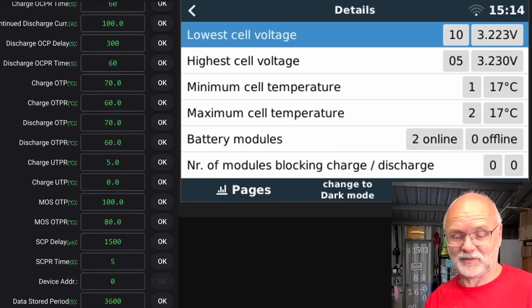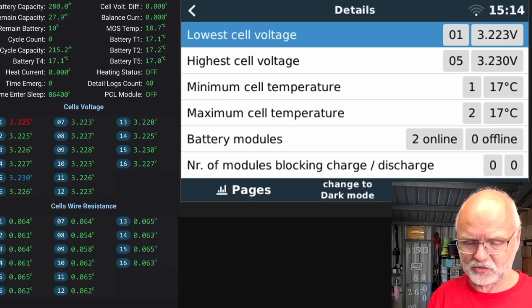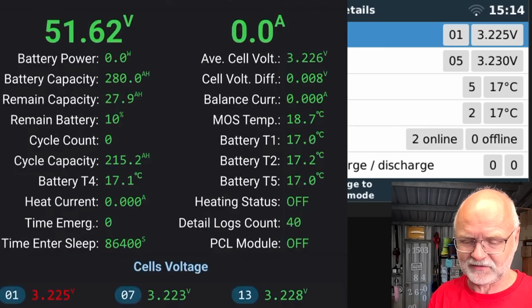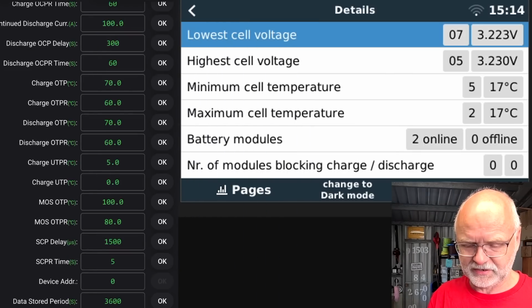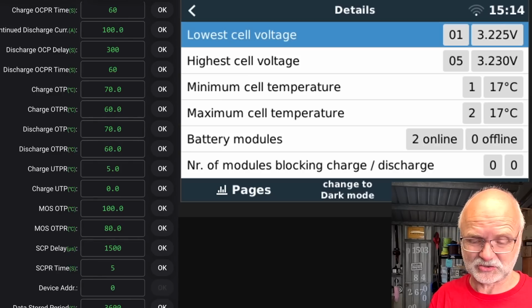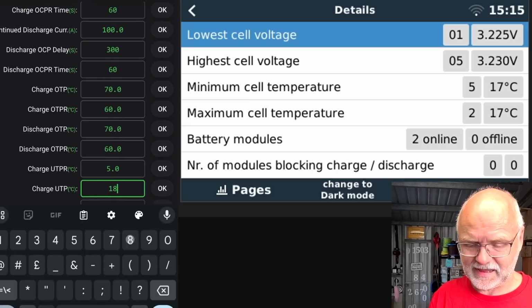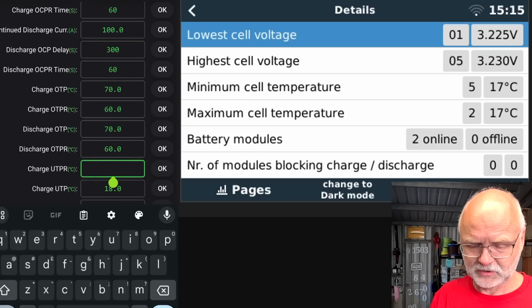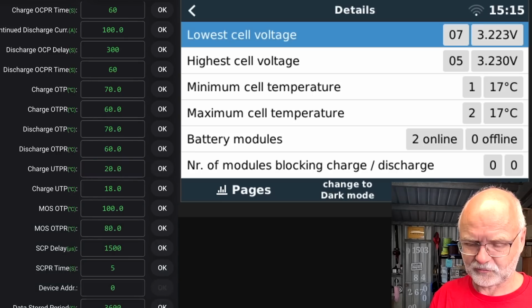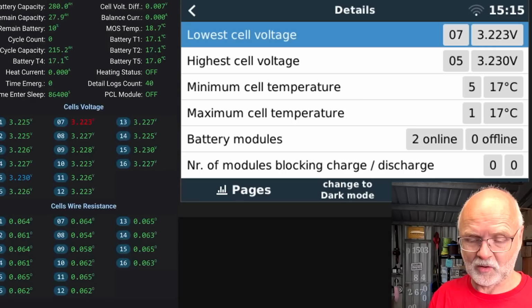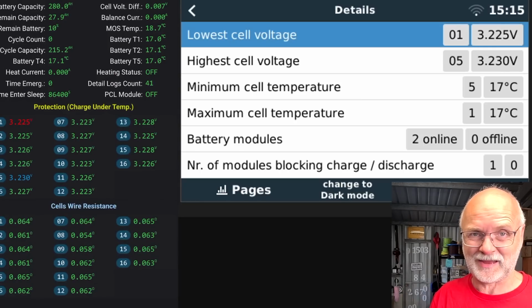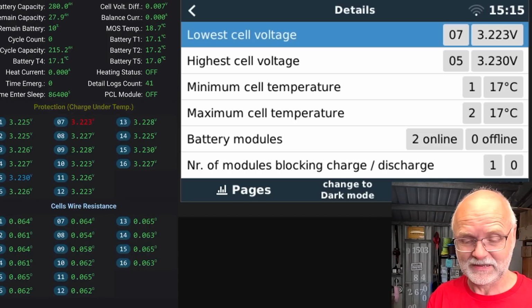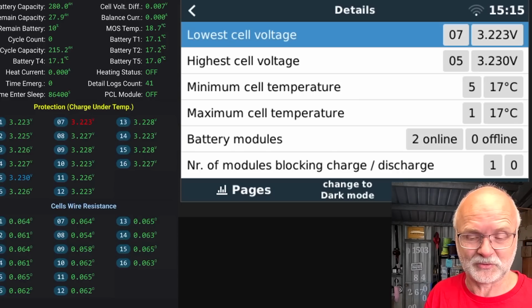Let's make the battery cold. I'm now logged into the master BMS. All the battery temperatures are around 17 degrees at the moment, so if I go in here and set the charge under-temperature protection, which is usually 0 degrees, to 18 degrees, and the recovery to 20 degrees, this will trigger an under-temperature protection for this one BMS. As you can see here, protection: charge under-temperature, because all the cells are under 18 degrees, as I just set.